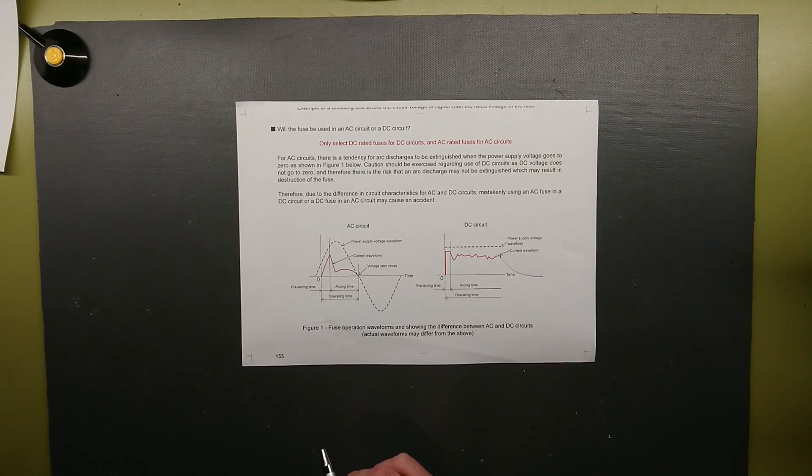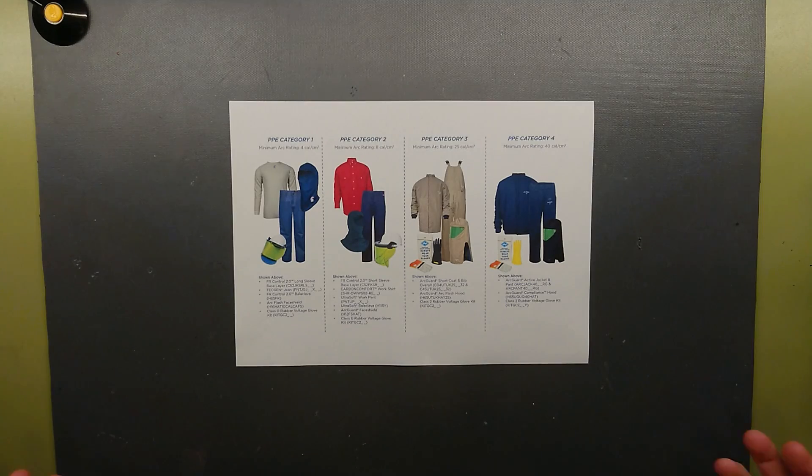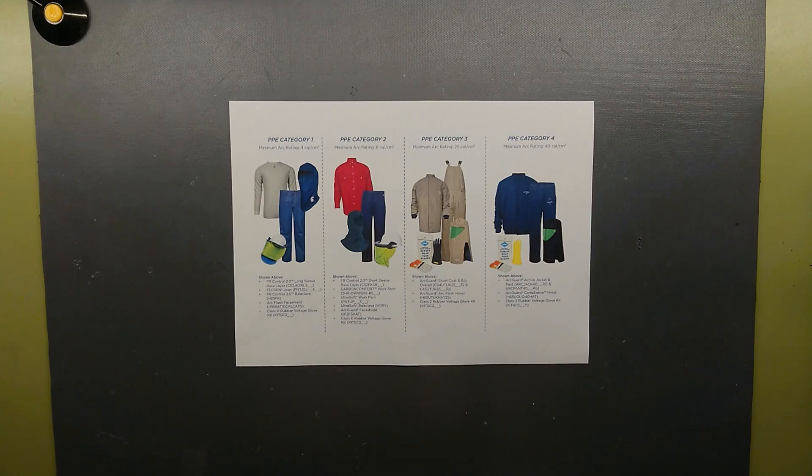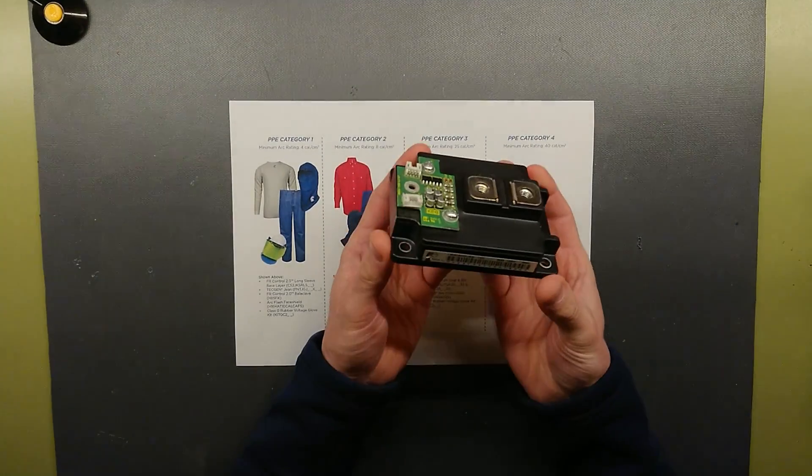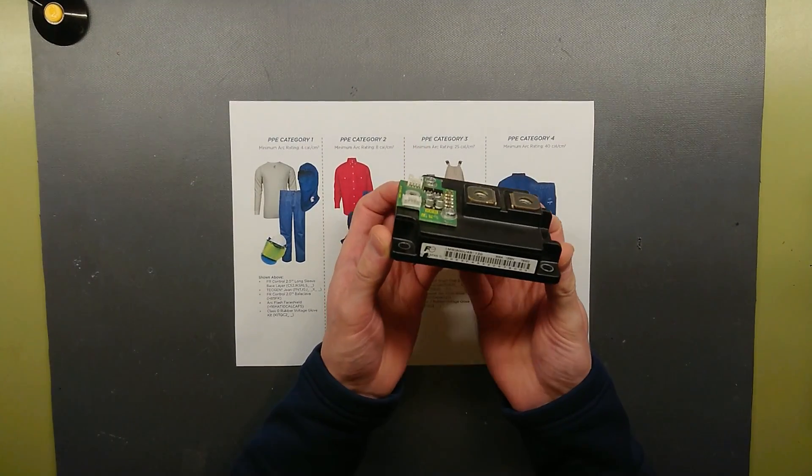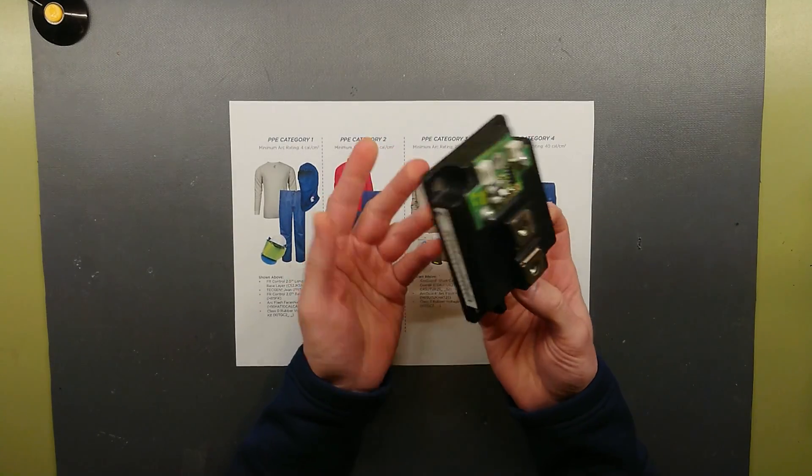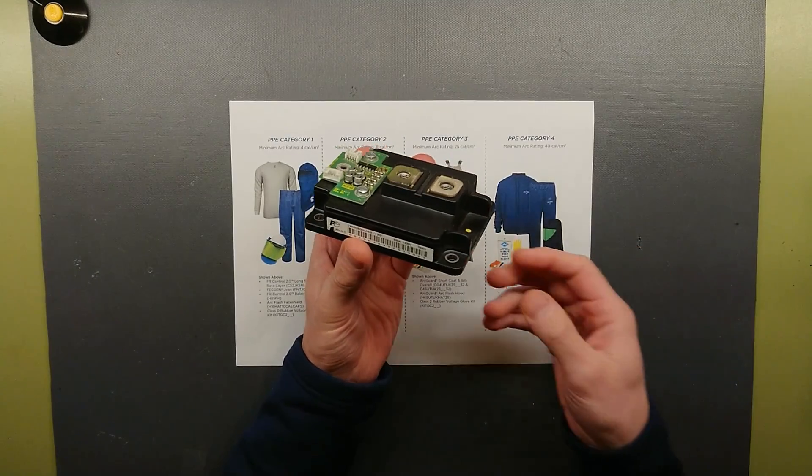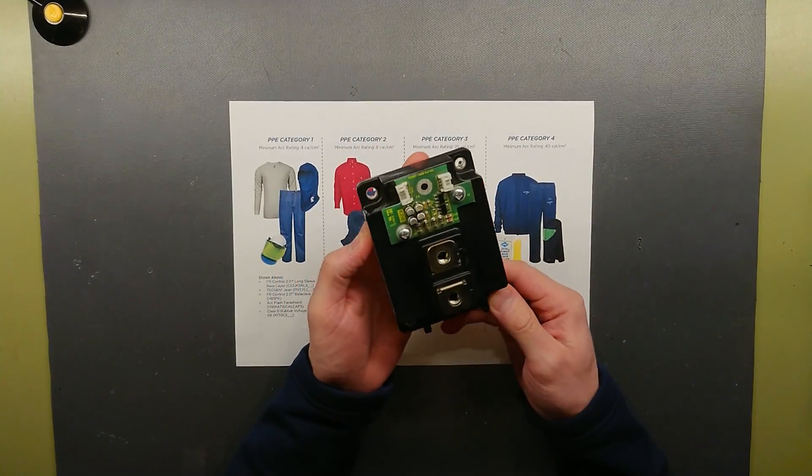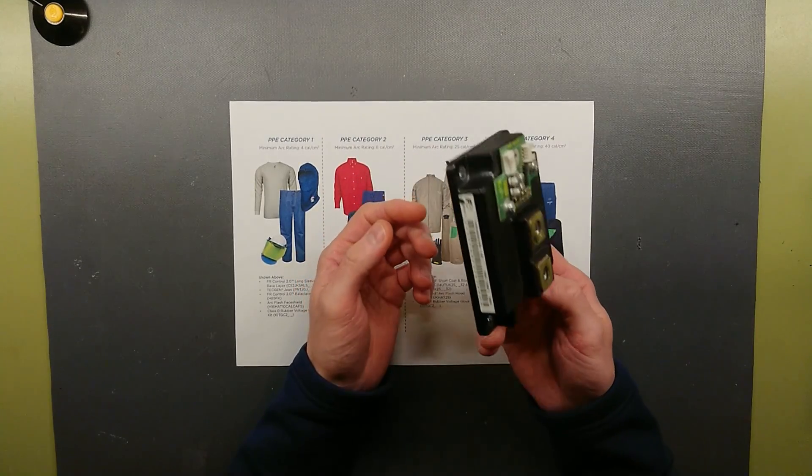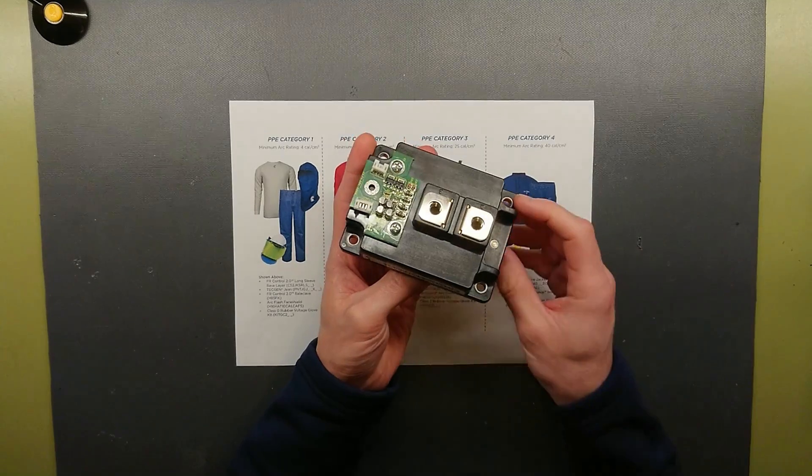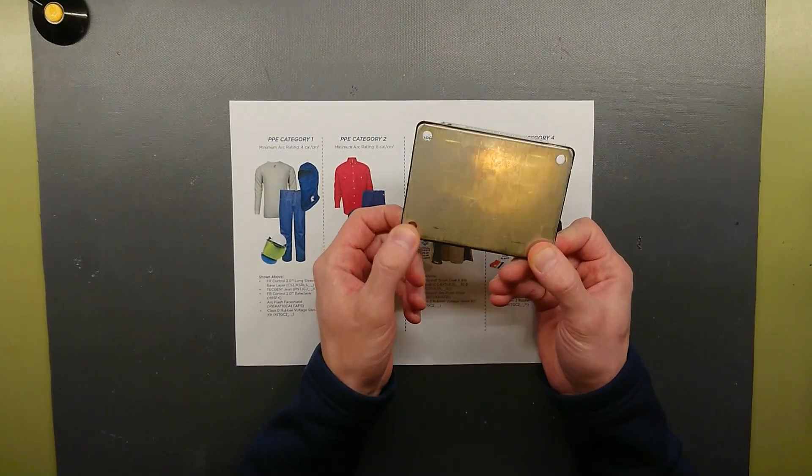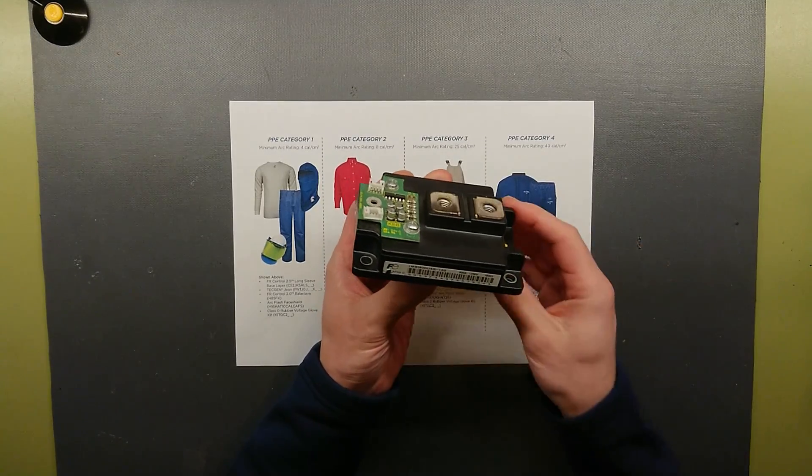What are the reasons that we want to use current limiting fuses or current limiting breakers? Originally we would just do it to protect these. This is an 800A IGBT brick and this is rather expensive if you have to buy these new or replace a whole drives full bridge of these.